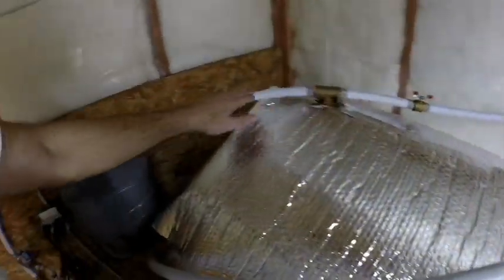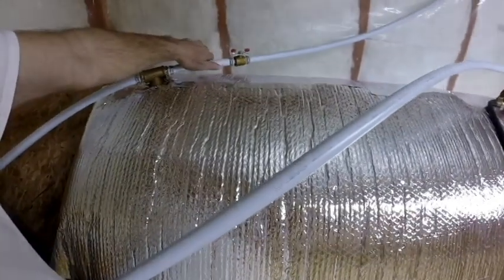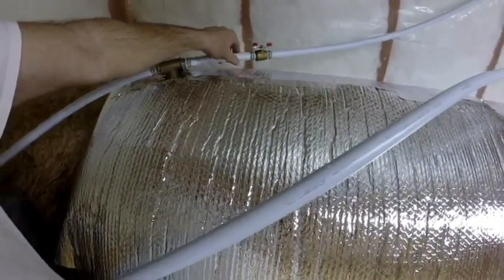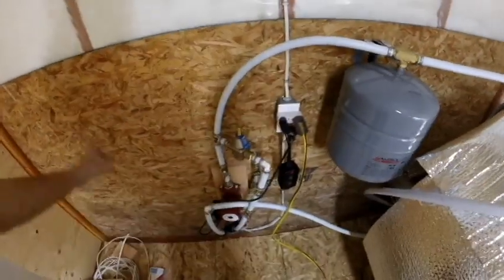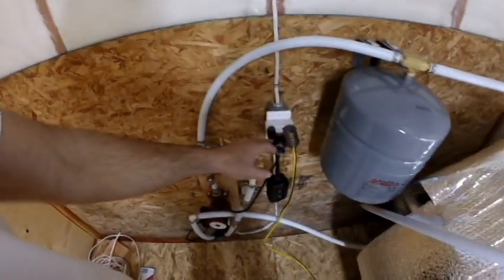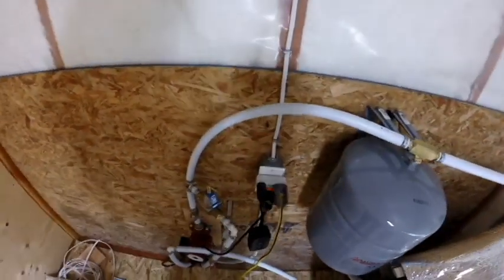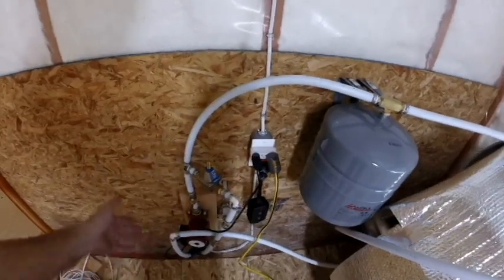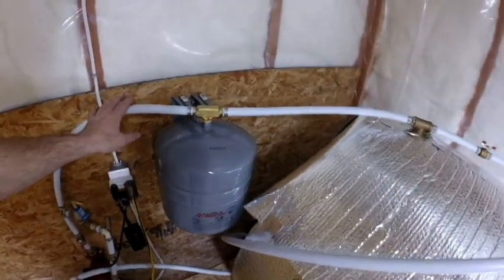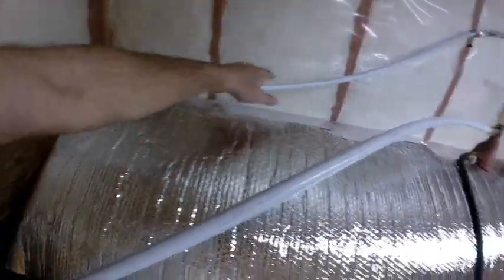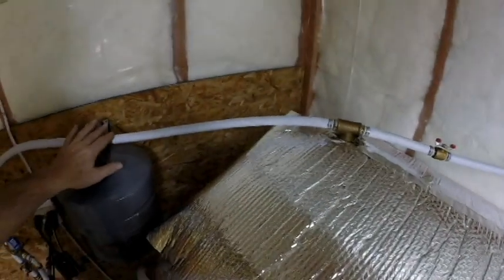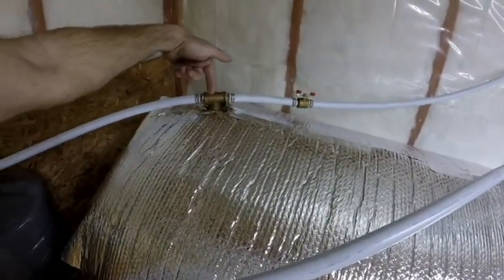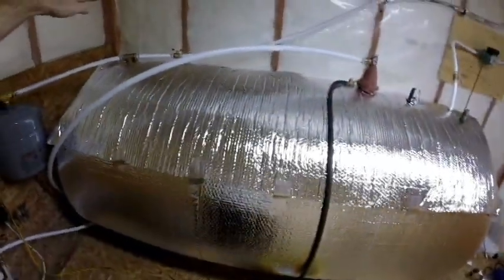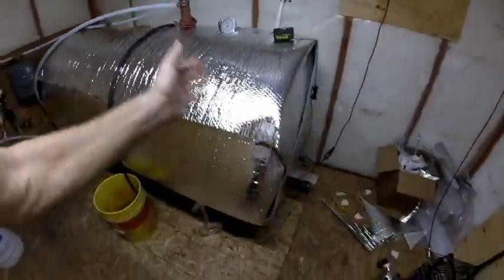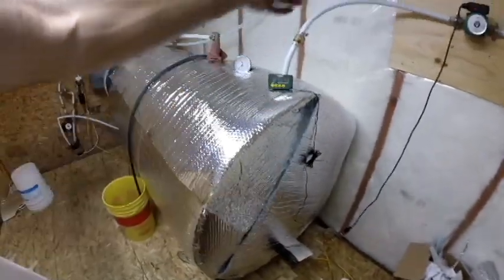So when this is calling for water, now the water, instead of going into the tank, will bypass right through this T straight into the system. So you're getting the hottest water, which right now is at 190 degrees approximately, going straight through into the pump, into the house, returns back to the tank. When that system stops in the house, the light goes off here on that plug. It stops this pump, the house pump stops, the water no longer flows through here. So then what happens is the water coming from the shop, instead of being used through this system, now goes down into the storage tank, from where the hot water goes in the top and has to push all the cooler water down to this point where the cold water is being drawn up out of this side.